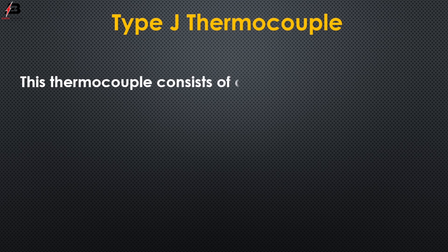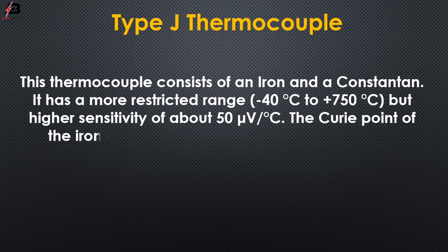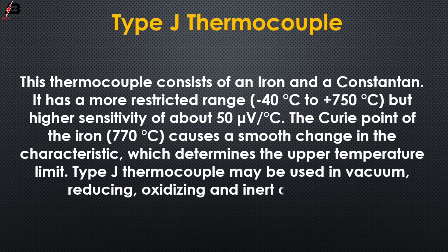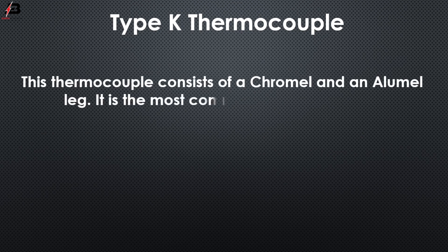Type J thermocouple: this thermocouple consists of an iron and a constantan leg. It has a more restricted range of minus 40°C to plus 750°C, but higher sensitivity of about 50 microvolts per degree centigrade. The Curie point of iron at 770°C causes a smooth change in the characteristic, which determines the upper temperature limit. Type J thermocouples may be used in vacuum, reducing, oxidizing, and inert atmospheres.